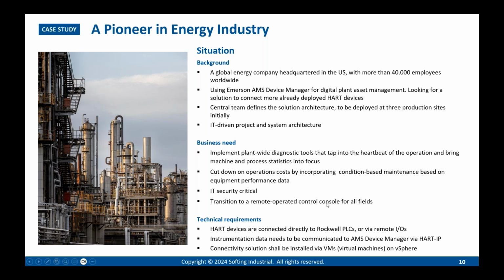Now, what were the technical requirements? They had the HART devices connected to Rockwell PLCs or via remote IOs, and they had the Emerson AMS Device Manager running on the HART IP server. Another technical requirement from their side was that the connectivity solution shall run on a virtual machine, VMware or Hyper-V. Here they wanted the VMware one, and those were the requirements they had.